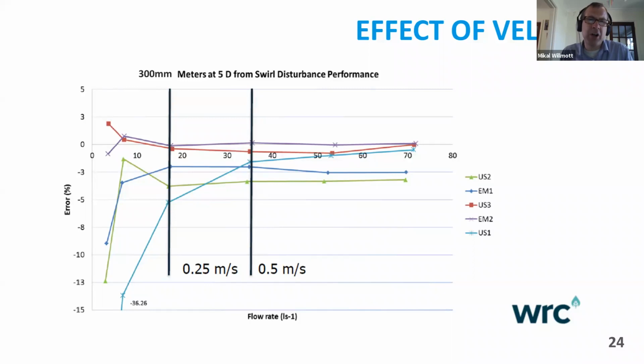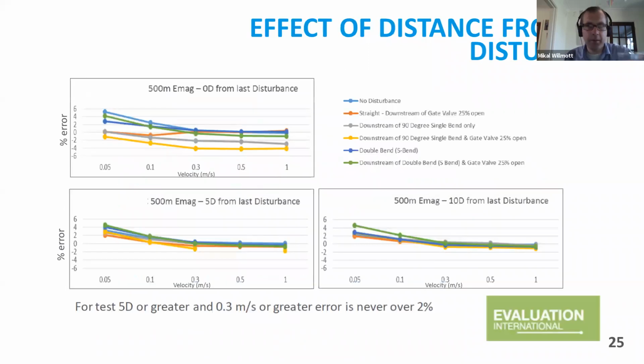However, if I was writing a design manual for an installation team, I would probably say the minimum velocity I want is 0.5. Part of the reason is that sometimes engineers like to take it down a little bit. So if I tell them 0.5, they might go for 0.4. Now, if I tell them 0.25, they might take me down a notch or two. So there's a bit of a safety margin there. But my recommendation would be to have your minimum velocity at 0.5 meters per second, and there's probably very little benefit in needing a higher velocity than that. Okay, Andy, if you'd like to move on again, please.